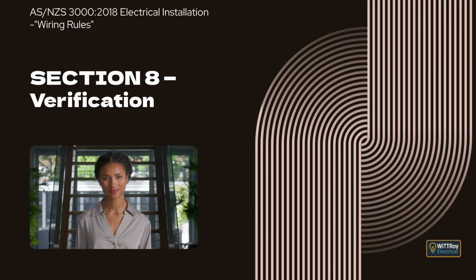Clause 8.3.2, Test Methods. This clause explains that AS/NZS 3017 sets out common test methods that may be used to verify, by testing, that a low-voltage electrical installation complies with this standard. It also includes minimum safety standards for test instruments. Testing must be carried out in a way that ensures the safety of the operator and other people nearby, and that test equipment is not placed at risk. The clause notes that the test methods given are reference methods, and other methods may be used provided they give equally valid results.